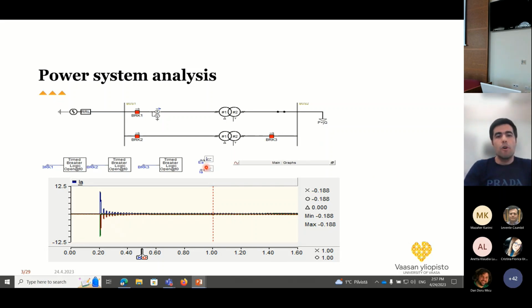Another example is about energizing a transformer in a substation. Since we want to energize this transformer, we have a current which is by far more than the nominal one. I mean, maybe it is 10 times more than nominal current. Since we have a differential relay in the substation, we should block this inrush current. And the behavior of inrush current, again, in this situation is above the x-axis, which means we have even harmonics, I mean second harmonic, fourth harmonic, and we can make use of such harmonics to block the differential relay in this situation.